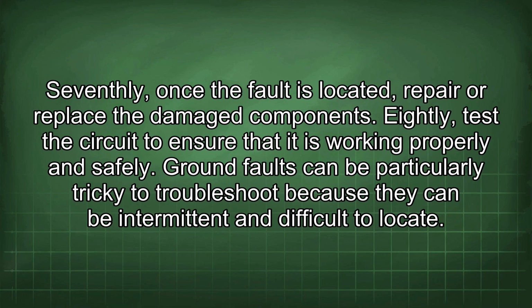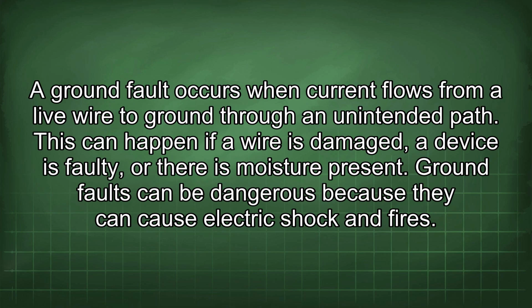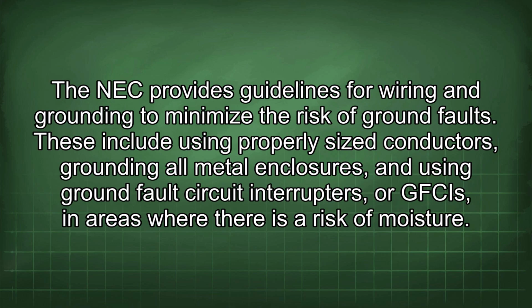Ground faults can be particularly tricky to troubleshoot because they can be intermittent and difficult to locate. A ground fault occurs when current flows from a live wire to ground through an unintended path. This can happen if a wire is damaged, a device is faulty, or there is moisture present. Ground faults can be dangerous because they can cause electric shock and fires. The NEC provides guidelines for wiring and grounding to minimize the risk of ground faults. These include using properly sized conductors, grounding all metal enclosures, and using ground fault circuit interrupters, or GFCIs, in areas where there is a risk of moisture.